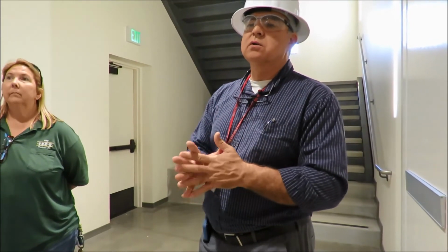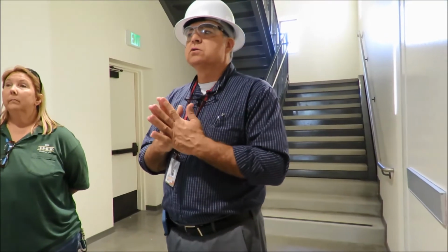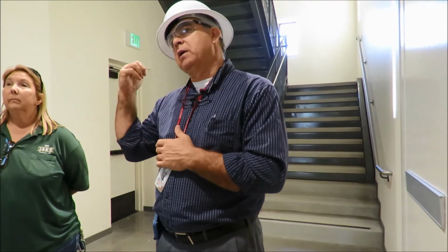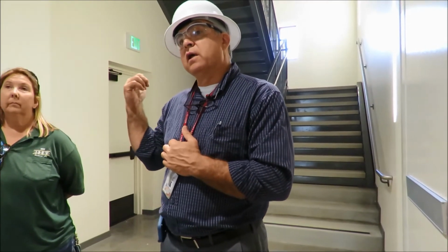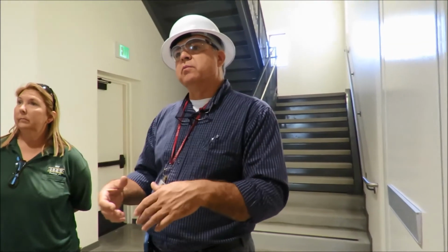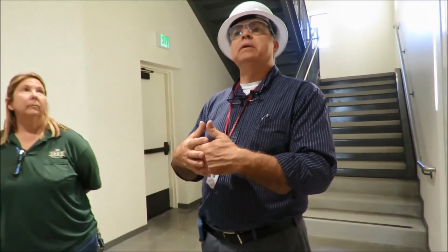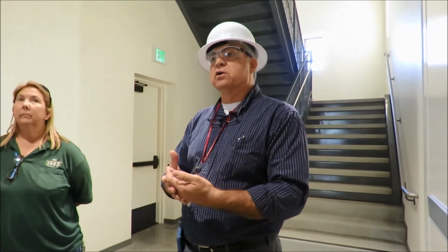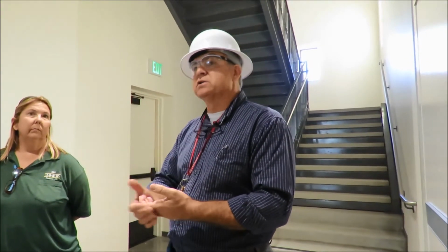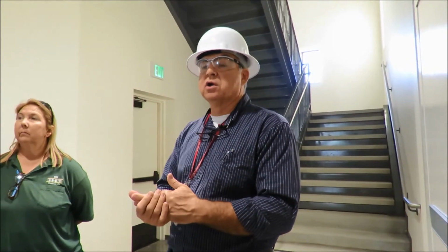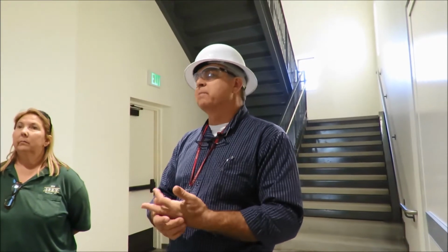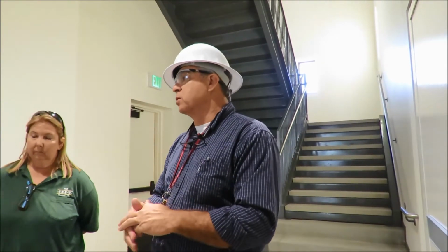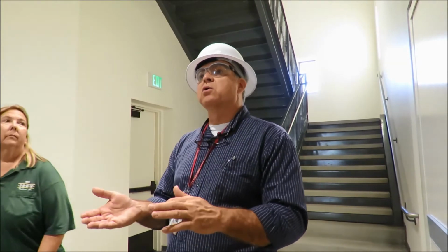But say there's an explosion in one of the labs. Sure. We kind of walked it before you came in, and we have a fire in that little room there. There's not going to be any audible alarm until at least 90 seconds after the sensor reaches temperature. But say it never does. The room could completely get filled with smoke, so you're depending on the smoke sensor.